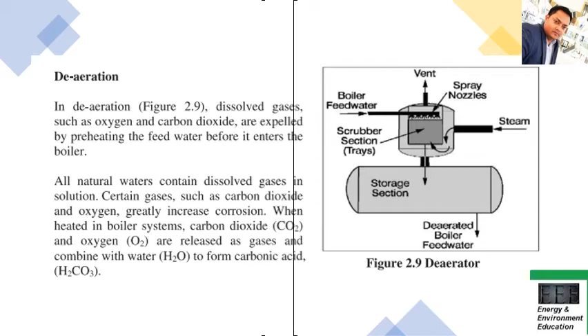All natural waters contain dissolved gases in solution, and certain gases such as carbon dioxide and oxygen greatly increase corrosion, and for that reason you need to preheat the water such that these gases which are dissolved inside the water come out, or you can say are expelled, friends. This is the process of deaeration, friends, and it's very easy to understand.